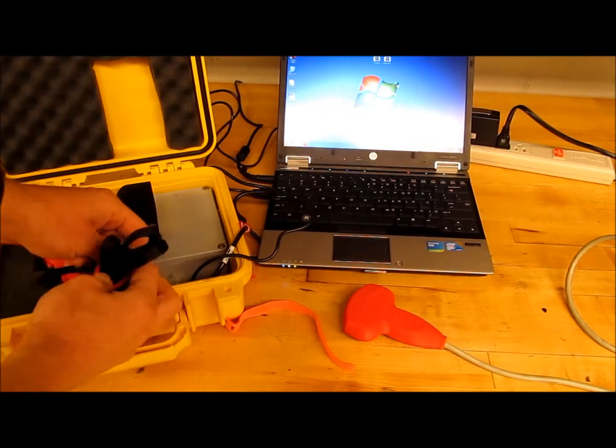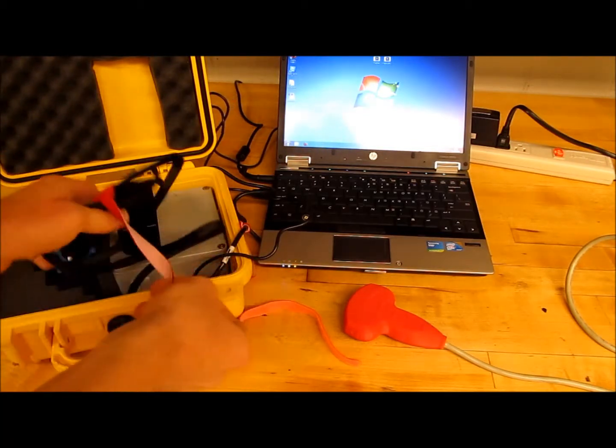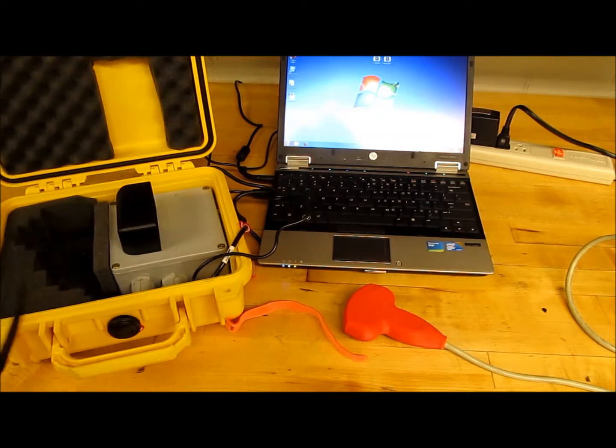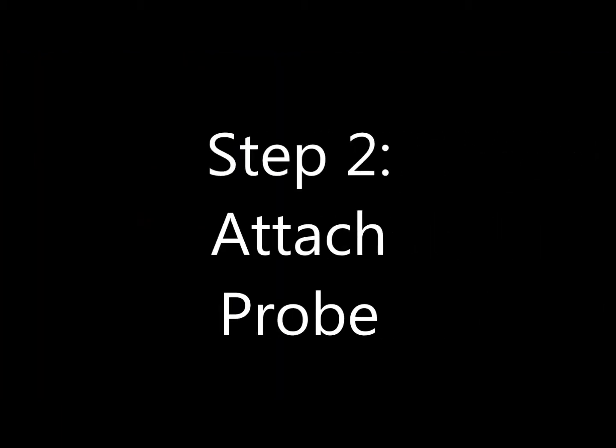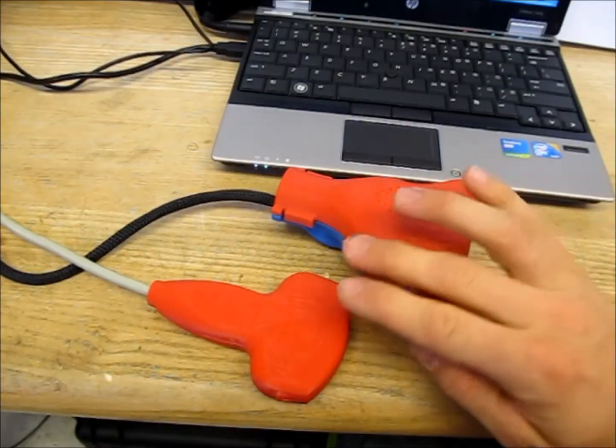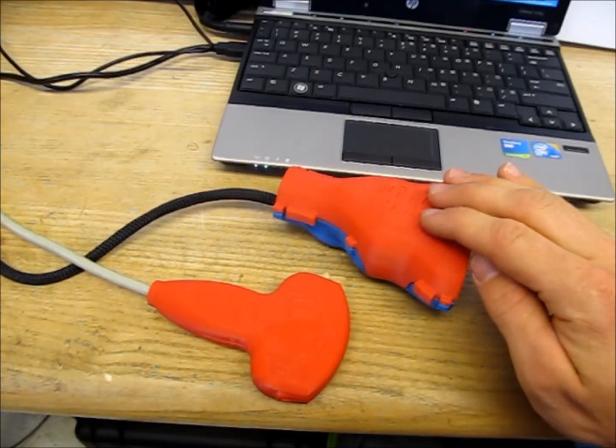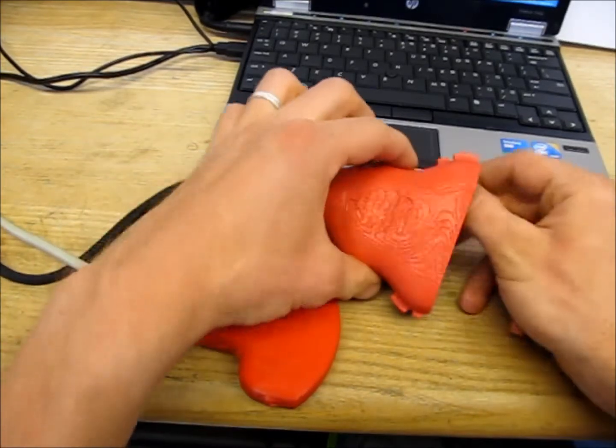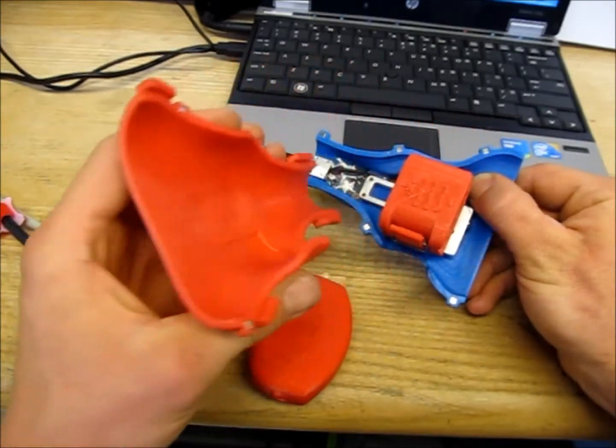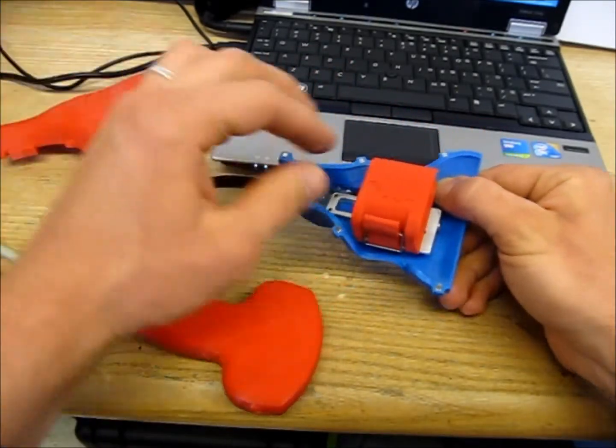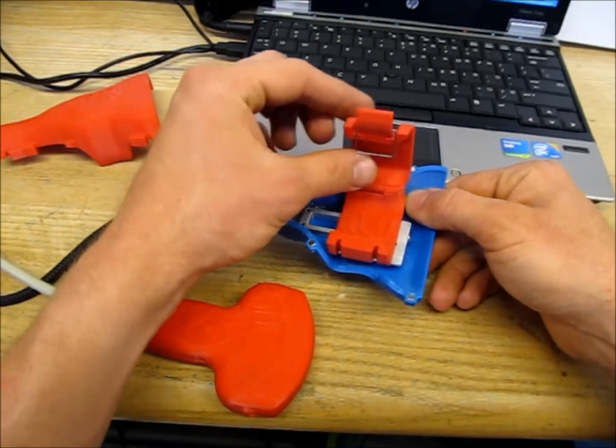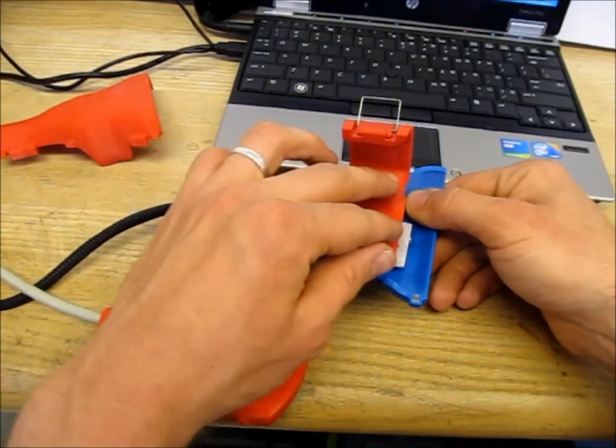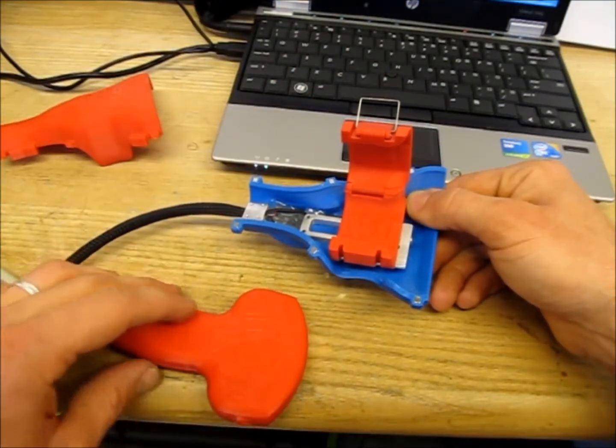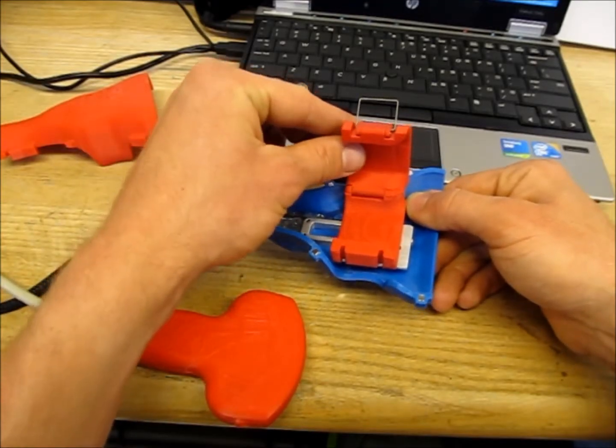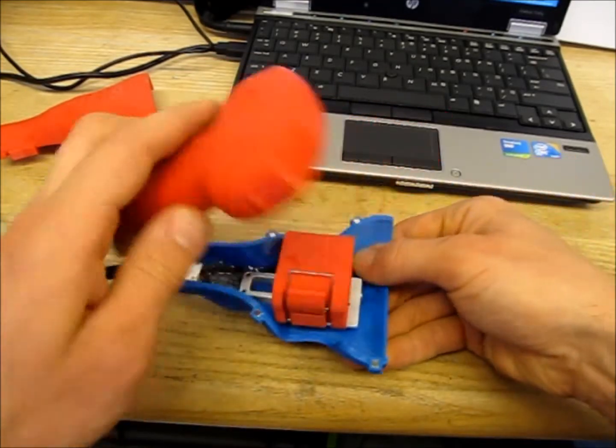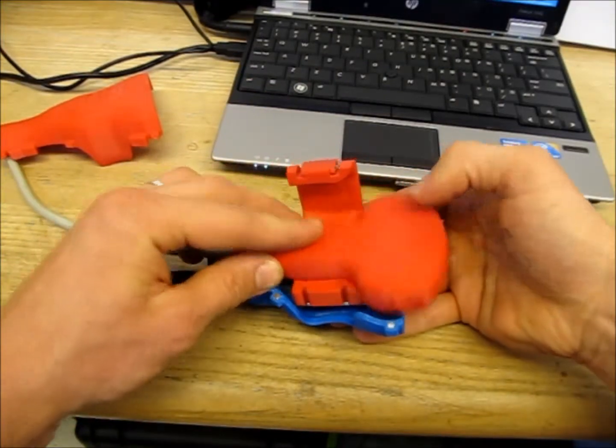Now the next step is to attach the ultrasound probe to the device. I'm going to demonstrate how we do that. First, we remove the top shell from the device, which is just attached by some magnets. Then we lift the top part of the clamp. We refer to this red piece as the probe clamp. So first we pivot the top half of the clamp up. Then we insert the ultrasound probe.